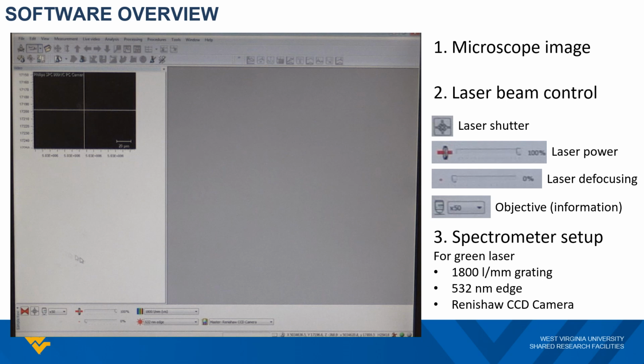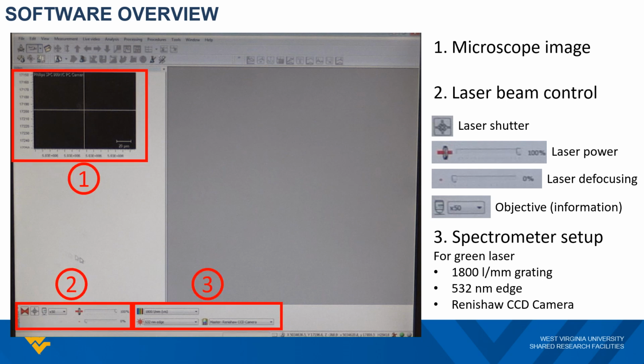The software interface has three areas. At the upper left corner, we have the image window, which will show the real-time image from the samples. Since our microscope is not equipped with eyepieces, you will need to use this image window to observe and align your sample.